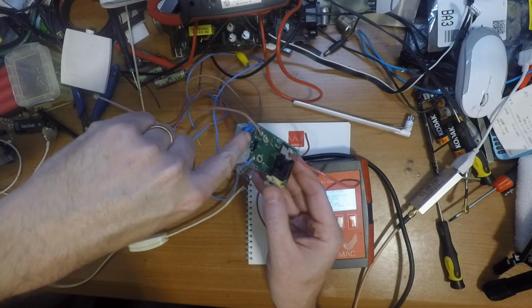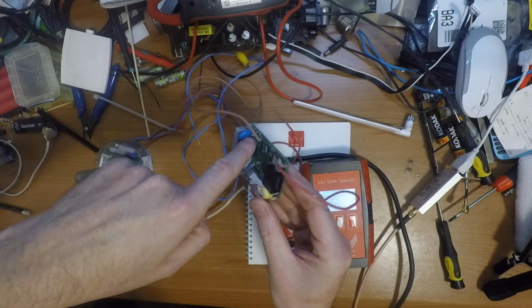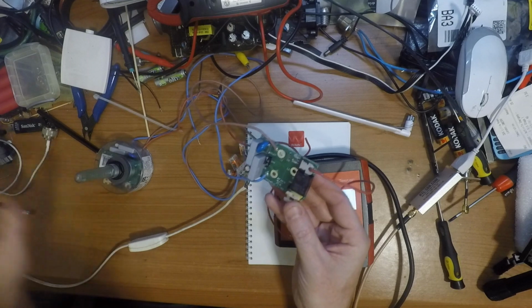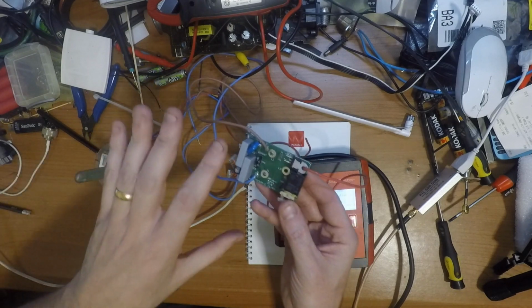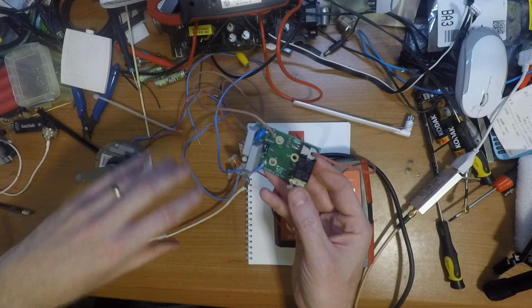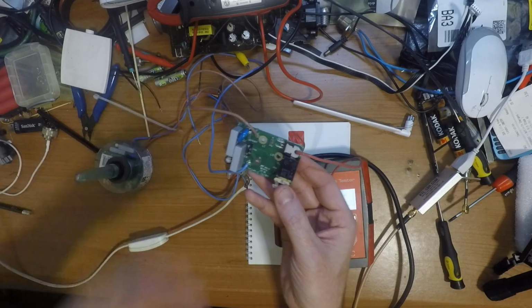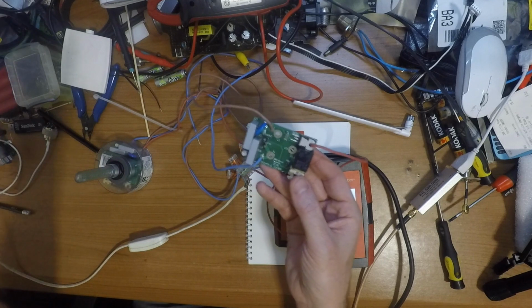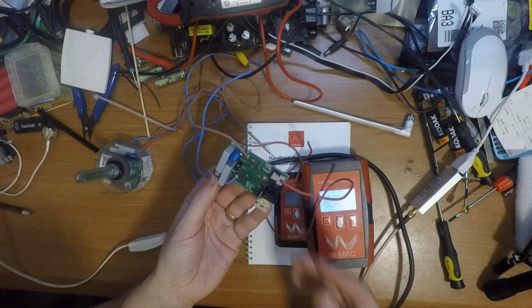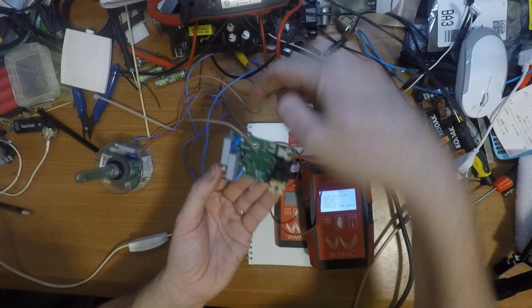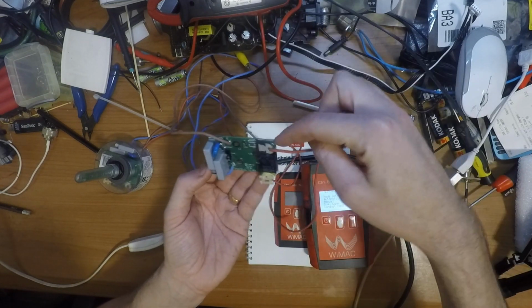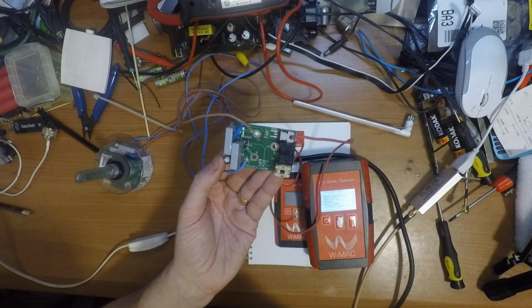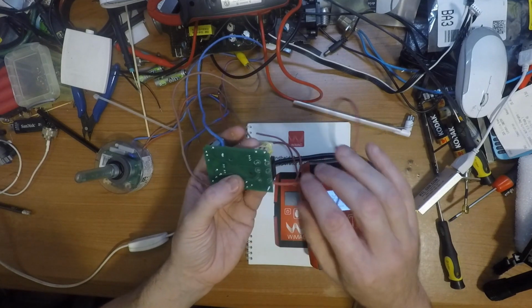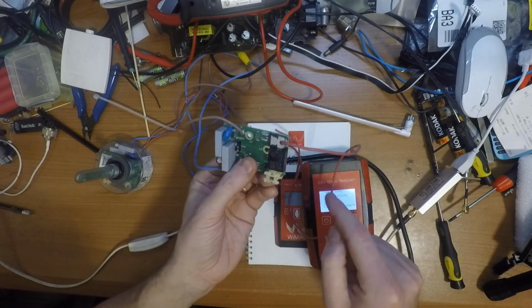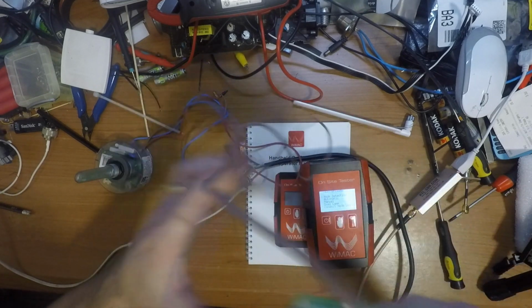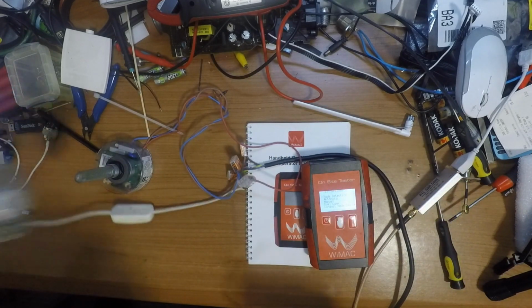The live goes via a little shunt here. With that shunt there, they can measure the power that the lamp's using. That's really good because it means if a light should be on, but it's using no power, it's faulty, and they can detect that and send people out to have it replaced. The live comes in here, it comes around here and it goes via this SCR and this relay here. And the switched output comes out of the relay, across the track here, and into this red cable, which we have connected up to our light.